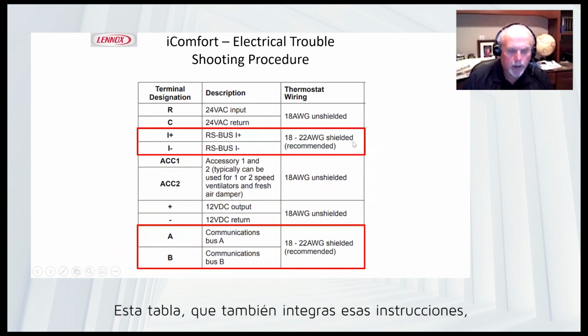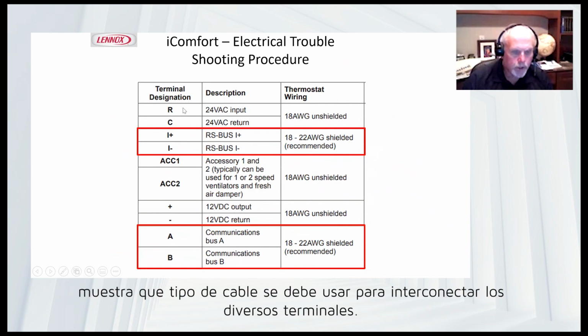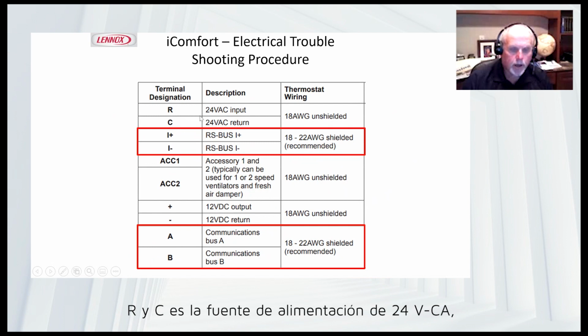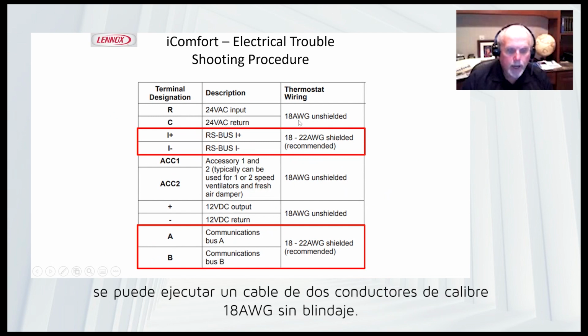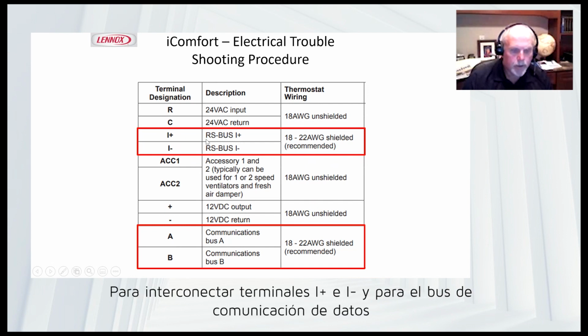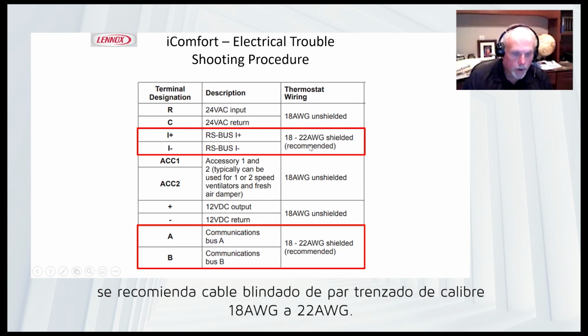This is also in the installation instruction by the wiring diagram, kind of showing you which wire to use for which terminals. R and C is your 24-volt power supply. You can run regular 18 gauge two conductor wire, unshielded, for that. Your I plus, I minus, we are recommending that you run shielded twisted pair stranded wire.